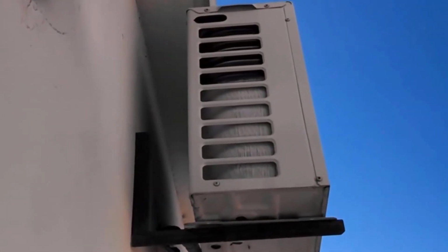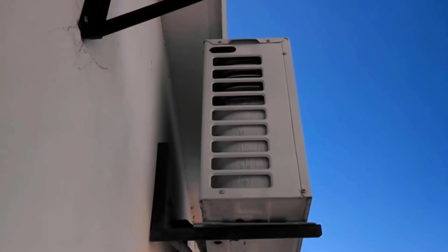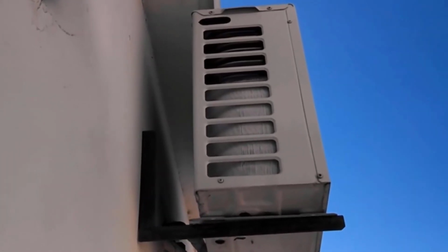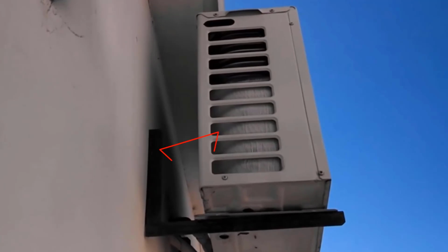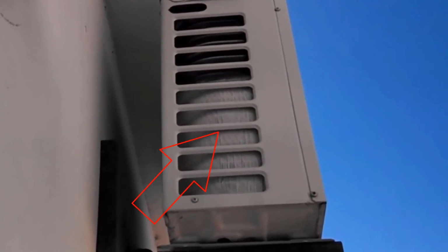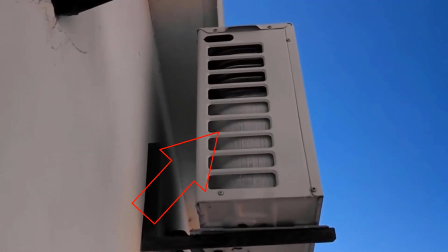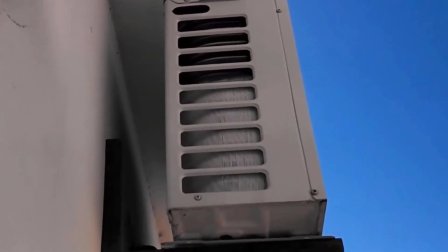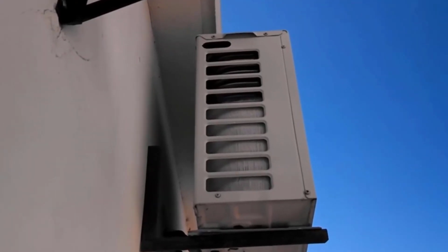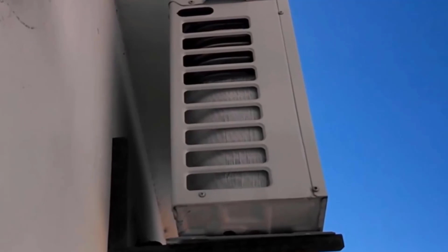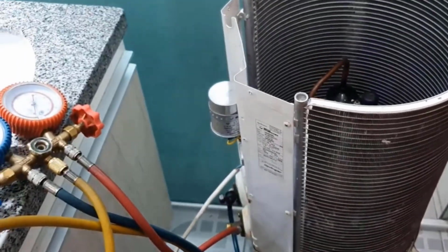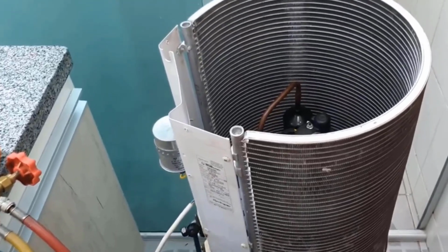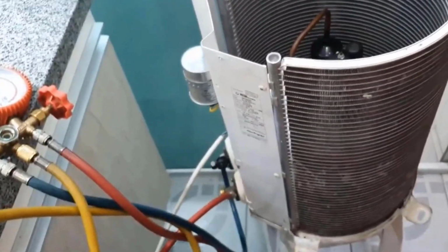Now, let's imagine that the error persists for a while. In this case, what can you do, even if you are not a technician? Take a look at the external condenser and check if the coil, which is that copper tube inside the equipment, is frozen. If there is a visible layer of ice, this means that the sensor is working, but the equipment is actually experiencing freezing. In this case, it is not a sensor problem, but rather related to the gas flow.